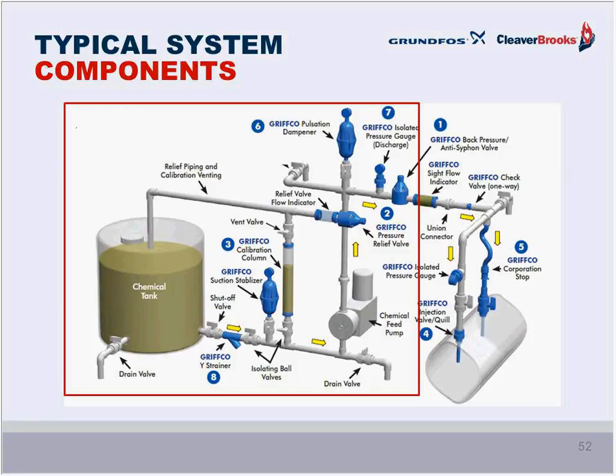Number 2, pressure relief valve. Not specifically for pump protection, but more for the system piping protection. If a downstream valve is accidentally closed, a relief valve will allow the flow back to the suction side of the pump, or it can be directed directly to the chemical feed tank. An isolation valve between the pump discharge and the pressure release valve ensures a clear path to the pumped liquid in a blockage situation. These are, after all, positive displacement pumps we are working with, so something will have to give, and that's when we have that pressure relief valve system.